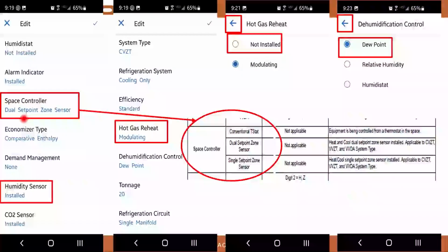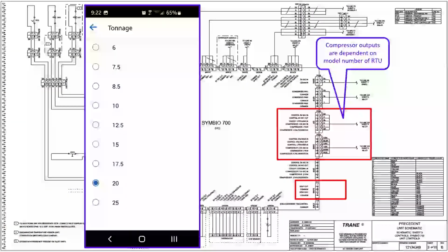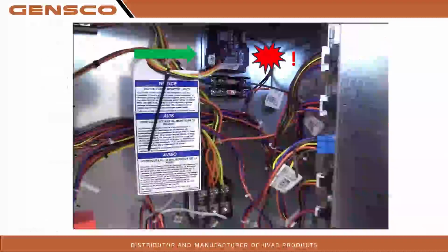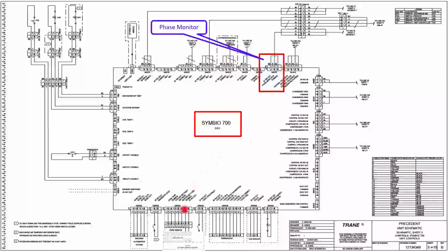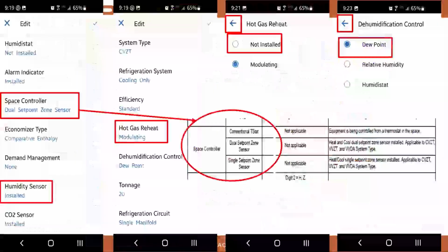Space controller, again, they come for dual set point zone sensor. So if you have it under the dual set point zone sensor, it is going to be looking for signals right here. So if you have a 24-volt thermostat, you're going to be sending signals right here, and it's going to be looking right here. It's not going to do anything. So you're going to come in here, you're going to tell it it has a conventional thermostat, and now you can jumper it out right there, or do whatever you need to wire it in for a normal thermostat.